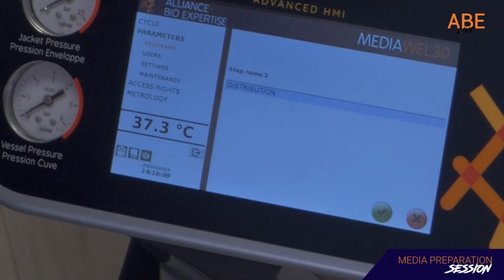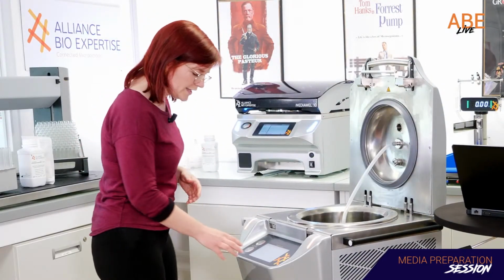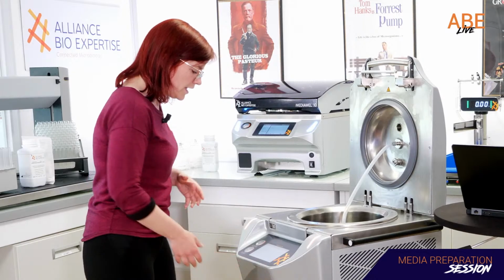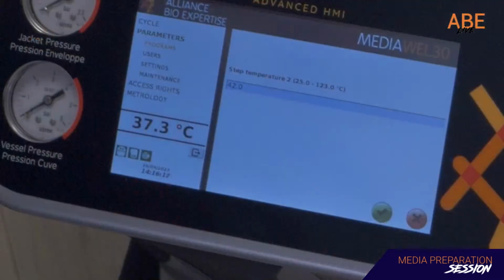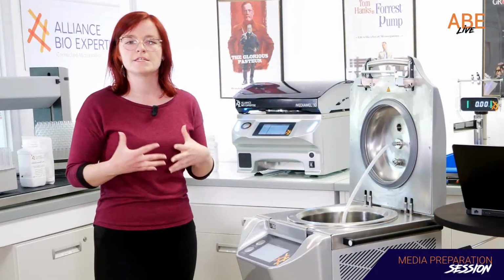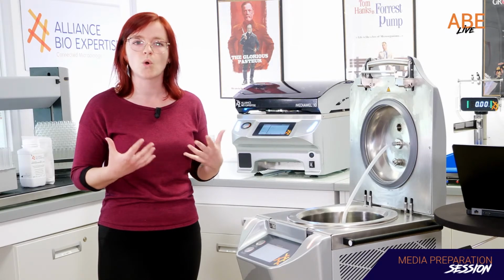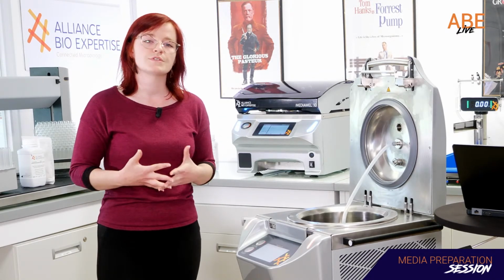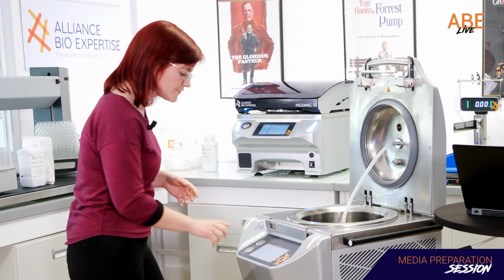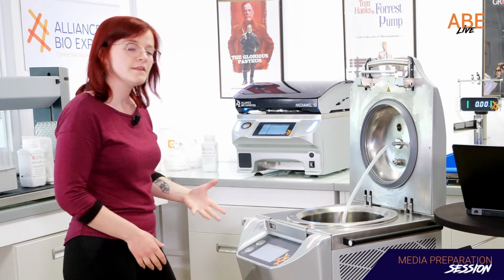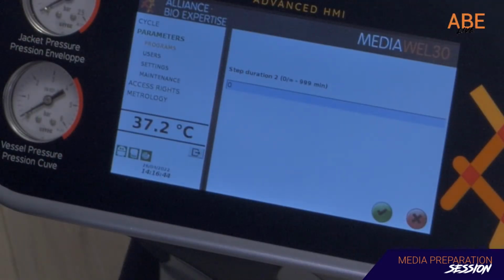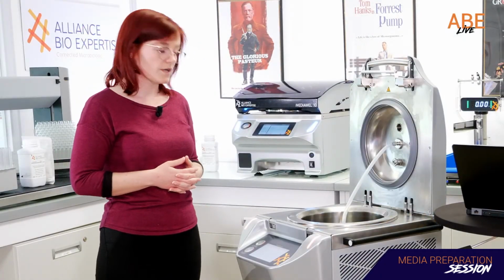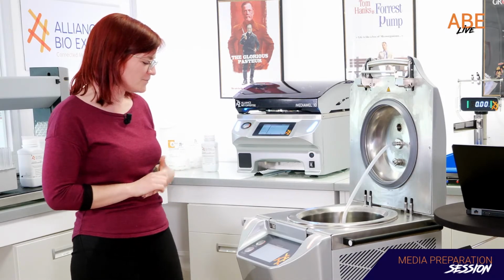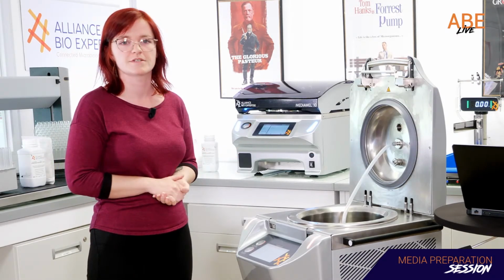Then the second step will be the distribution. The name is already available. It will ask me the temperature of the distribution. It depends on the media, but usually we see with the media preparator a distribution temperature of 42, because thanks to the mixing system and the heating system, the heat is kept during the whole distribution process. So you can distribute directly as close as possible to the solidification point. So here we can keep 42. And then you can also indicate the time you want the distribution step to last. So it can be either infinite or a specific time.